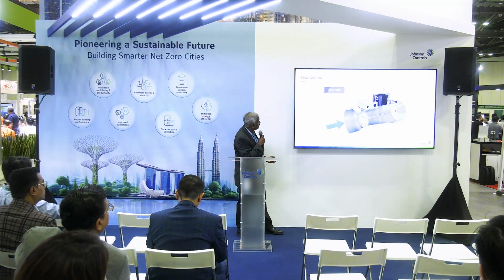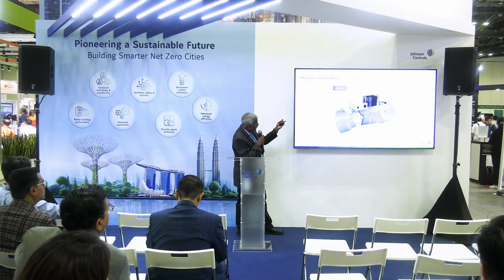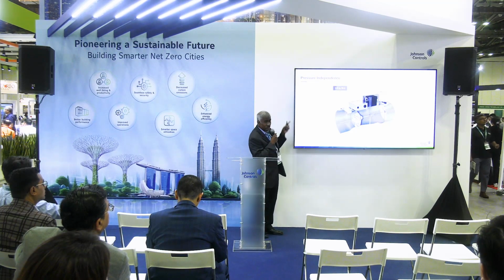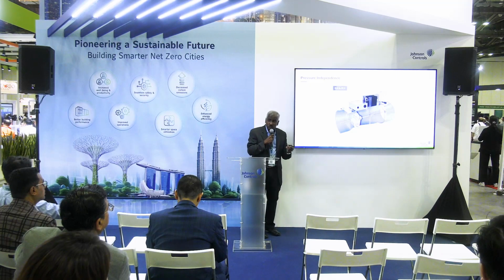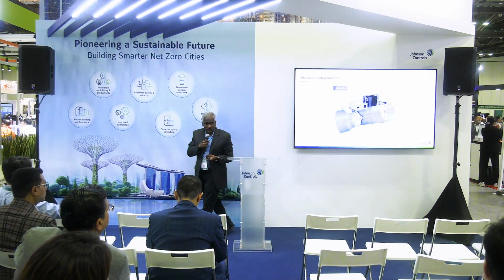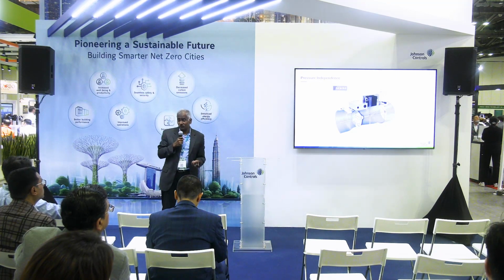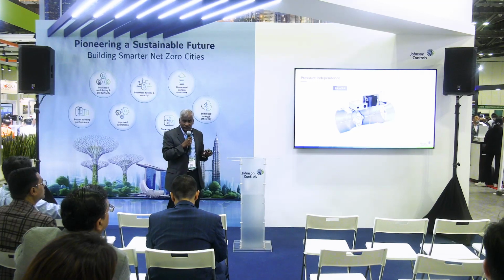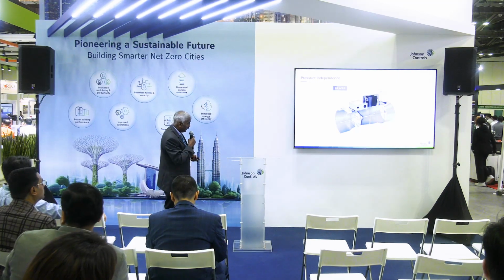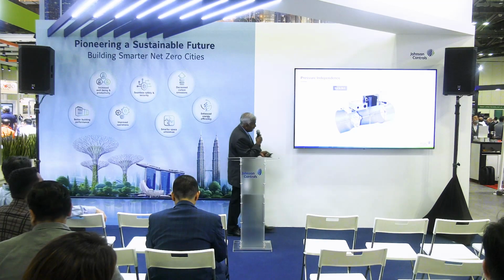As for the flow control, now this is where the criticality comes in, right? The pressure independence. Whenever someone is opening a door, let's say you're operating a room and the nurses are opening a door, you still have to maintain a positive or negative pressure, right? Be it in the OT room or in the isolation room, and see how it works, right?